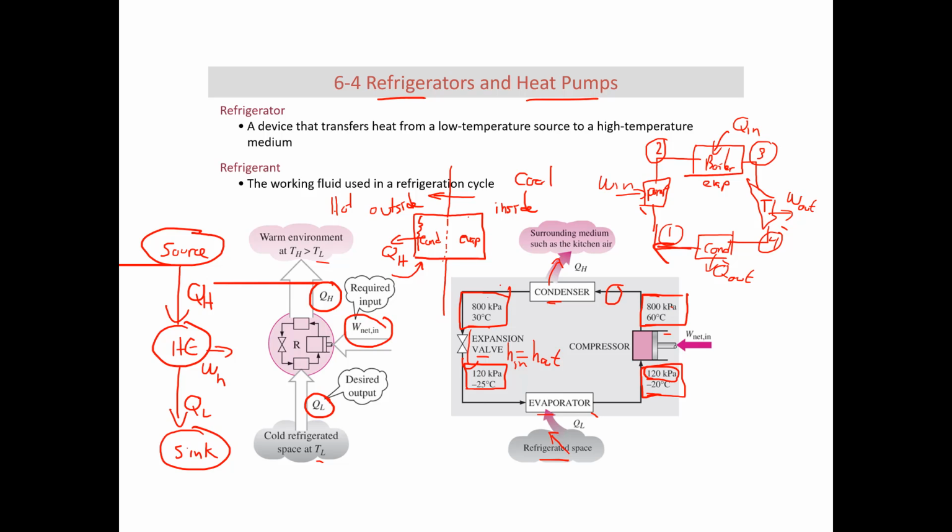to a liquid here. And the way to do it is that this pressure has to be at such a value that the corresponding saturation temperature is hotter than the outside air. Right? So I have TH, this is the temperature outside. In this case, it's T ambient. So my outside temperature, let's say it's 100 degrees Fahrenheit outside.